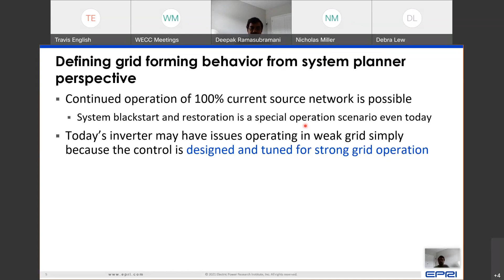As Nick mentioned, inverter-based resources that have been designed and tuned to operate in a strong grid can have issues in weak grids, because the design rules that have been applied to them were from the perspective of a strong grid, which means that if a weak grid manifests, they could have issues. And in that aspect, a phase lock loop is just one part of the entire control architecture in order to obtain synchronization. It's not the main or the sole cause of instability. There are other control loops that react and play a role in causing instability. Yes, the phase lock loop plays a role, and one can determine instability by looking at the phase lock loop and its performance, but at the same time, that can be tuned and made more robust, and it can be designed to operate in a weak grid environment.